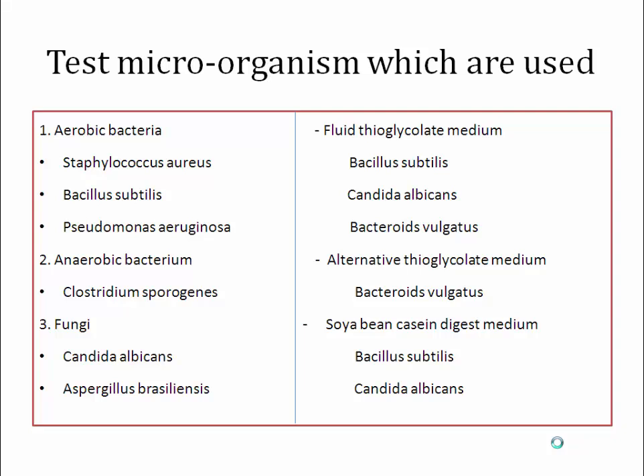Different types of test microorganisms are used for different media and conditions. For aerobic conditions, three microorganisms commonly used are Staphylococcus aureus, Bacillus subtilis, and Pseudomonas aeruginosa. For anaerobic bacteria, Clostridium sporogenes is used. For fungi, Candida albicans and Aspergillus are used. In Fluid Thioglycollate Medium, Bacillus subtilis, Candida albicans, and Bacteroides vulgatus are used. In Alternative Thioglycollate Medium, Bacteroides vulgatus is used. In Soybean Casein Digest Medium, Bacillus subtilis and Candida albicans are used.